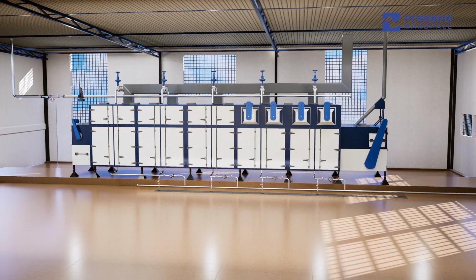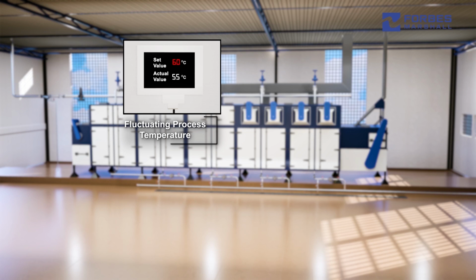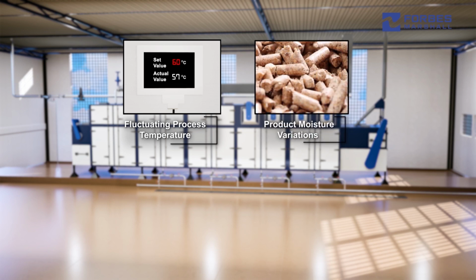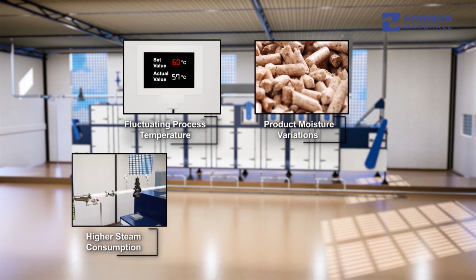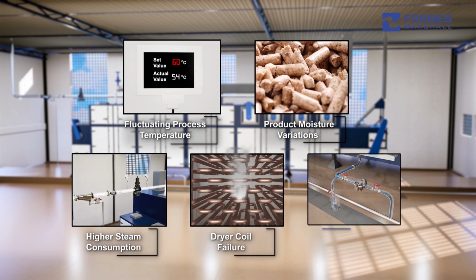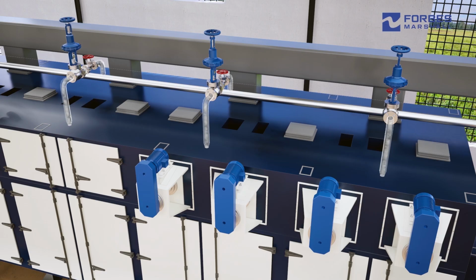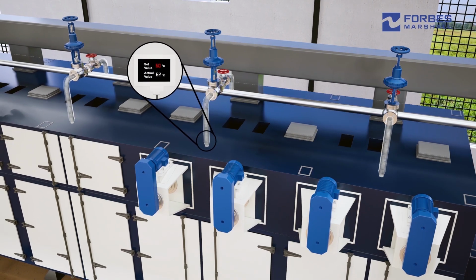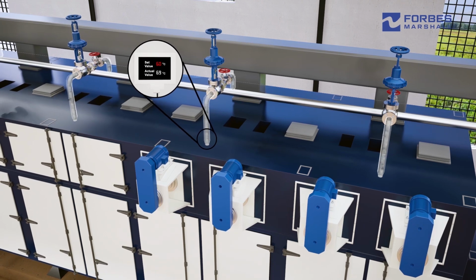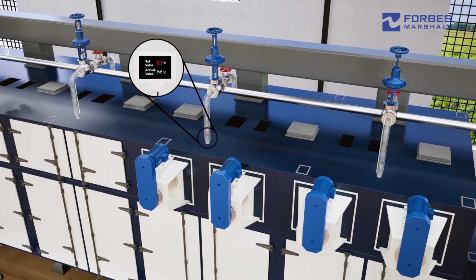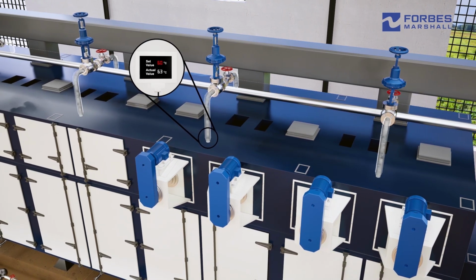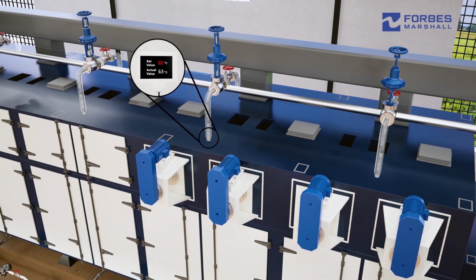Some common issues that feed plants face across dryers: fluctuating process temperature, product moisture variations, higher steam consumption, dryer coil failure, poor condensate recovery. Temperature overshoots in each zone due to on-off controls and excessive steam pressure lead to uneven drying and variations in feed outlet moisture.